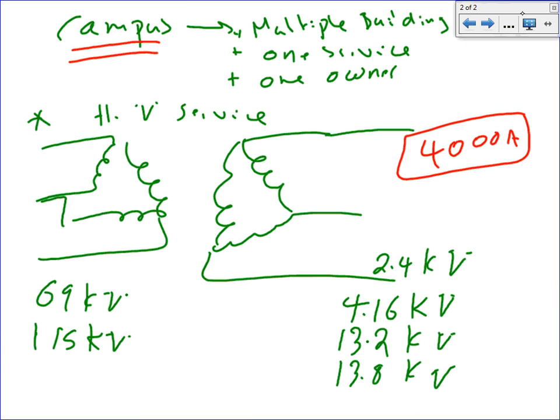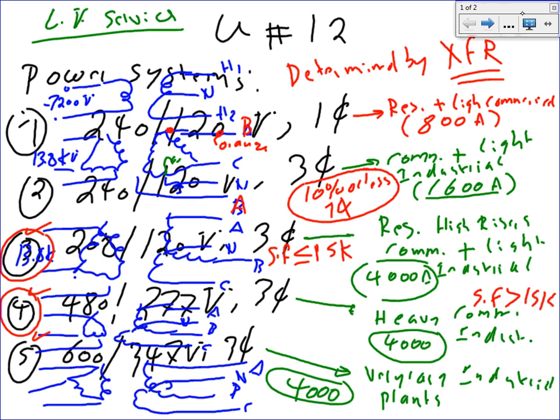Now, I want to bring to your attention, guys, one little thing. Here it says low voltage. What does low voltage mean? Equal or less than 600 volts. That's in the power language. Low voltage, in the power language, is equal or less than 600 volts.